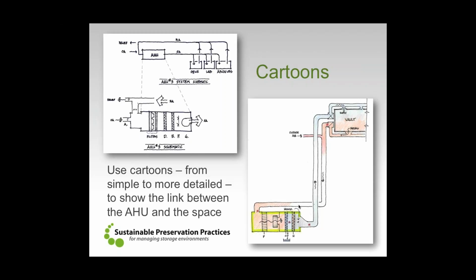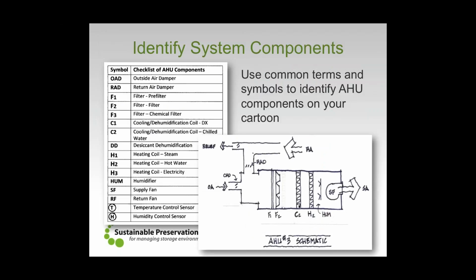But as we go through and we move from the zones into the cartoons, I think we discussed this a little bit last month, but we're going to use those cartoons to detail exactly which components we have and what the airflow is throughout the building. So where does it go, or what does it hit within that pattern of the loop as it goes from one mechanical system out to a number of different spaces. In those cartoons, as we said, we're going to identify those different system components and make sure that as we're thinking about operation, we know where the filters live and we know where the cooling coil and the heating coil are, what that arrangement is, where, if we have any, where does humidification occur, and also what those moving parts are. Remember, where is it that the dampers sit, and what type of control do we have over top of those.